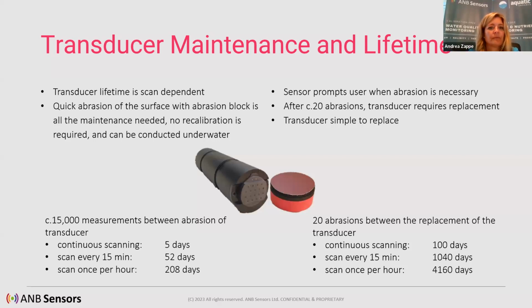So just like to touch base on the maintenance required for the sensor. First of all, it requires minimal maintenance, so ongoing costs are really kept to a minimum with the sensors that we provide. We need to abrade the sensor every 15,000 measurements, and that relates to, as you can see on the screen there in the bottom left-hand corner, if we're continuous scanning, today our continuous scan mode is every 23 seconds, the sensor would need abrading every 5 days.